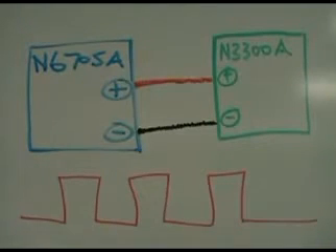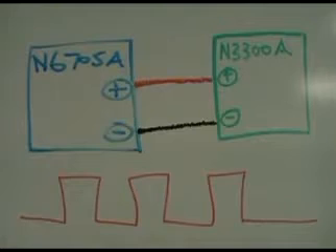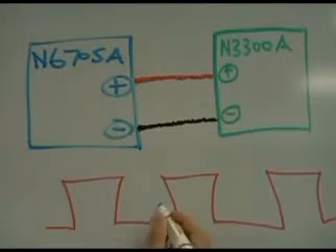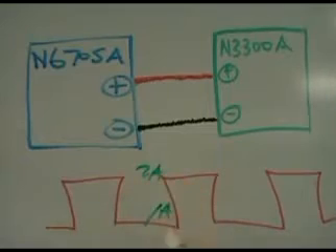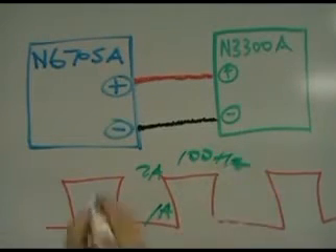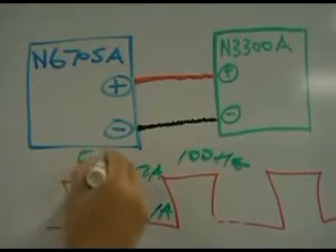The setup for this is really simple. We have an N6705A DC power analyzer connected to a N3300A electronic load. In this video example, we're going to go from 1A to 2A at 100Hz with a duty cycle of 50%.